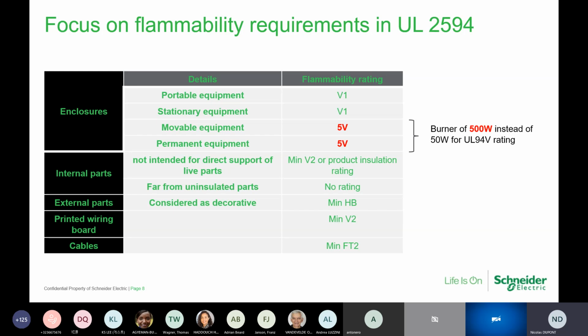So in the previous slides, we have seen in detail the technical requirements listed in the IEC standard for safety and reliability of charging station enclosure and plug-in sockets. But the situation is slightly different in the UL standard. And we decided to focus on the flammability specified in the UL 2594 and the UL 2202. So as you can see in this table, while the ratings are not very high for internal part or external component, both the movable and permanently installed enclosure should reach 5VA rating. And this rating is definitely the most stringent rating for the UL 94 flammability test.